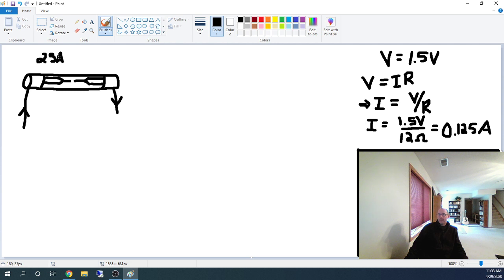You might say, well, my wire in my house says I'm supposed to only have a 20 amp fuse in here, but I'm annoyed because I keep drawing too much current, so I'm going to up my current to use a 25 amp fuse instead of 20. Here's the problem: the wires in the house are designed to withstand 20 amps, no problem, but 25 amps might be sketchy.